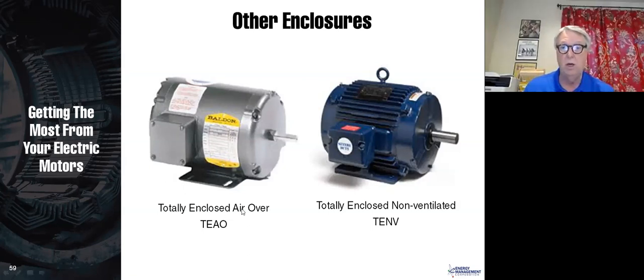So this is a totally enclosed air over. There's no fan on this thing. And generally we put this thing inside, let's say, the plenum of a heating, ventilation, air conditioning system. If it's in there and whenever the motor's running, the fan is blowing air and air is moving across that motor, then there's no reason to put a fan on the motor itself. So these are used in applications where the motor is mounted inside where the air is already moving, and it will get plenty of ventilation without having an additional fan.